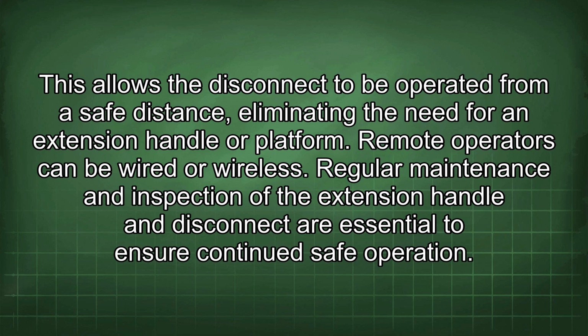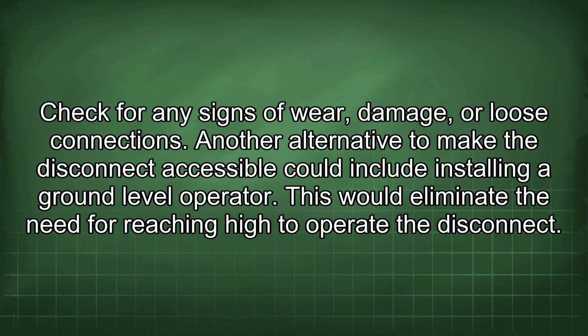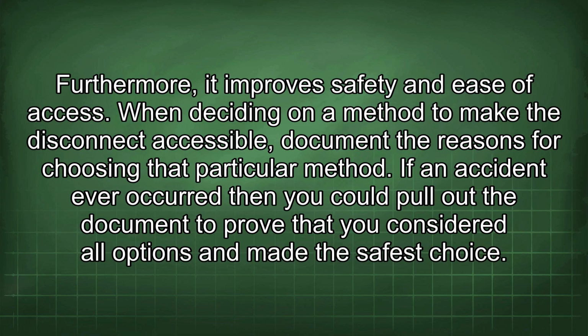Regular maintenance and inspection of the extension handle and disconnect are essential to ensure continued safe operation. Check for any signs of wear, damage, or loose connections. Another alternative to make the disconnect accessible could include installing a ground-level operator. This would eliminate the need for reaching high to operate the disconnect. Furthermore, it improves safety and ease of access.